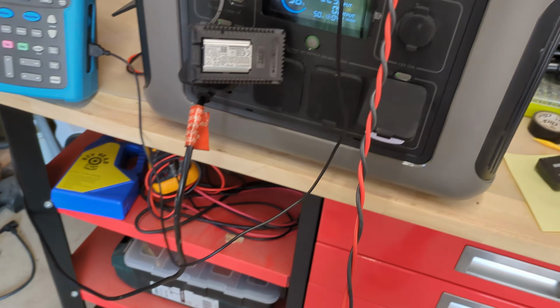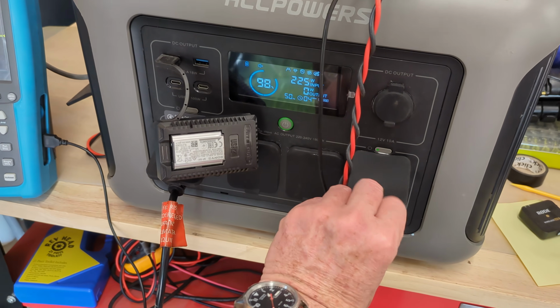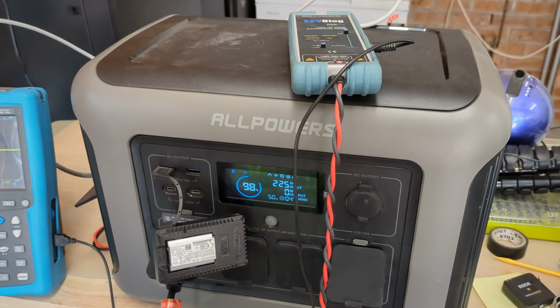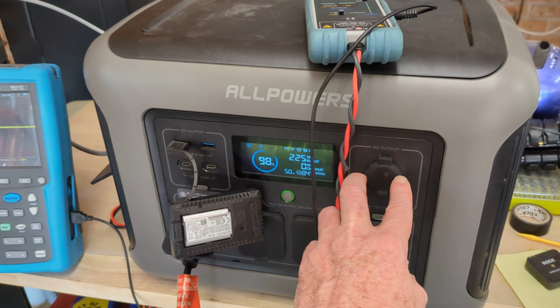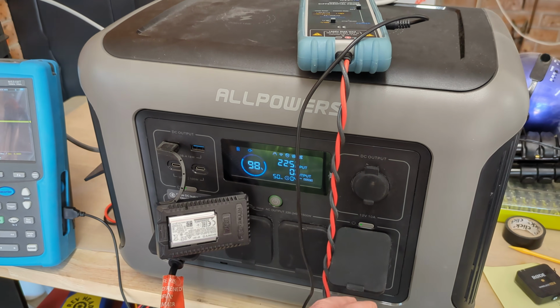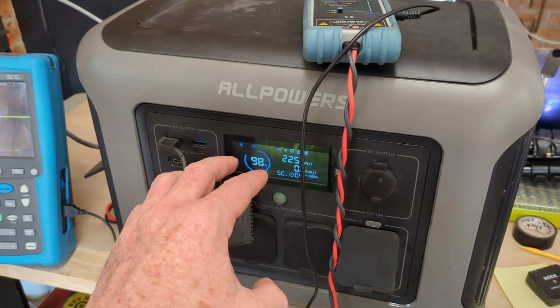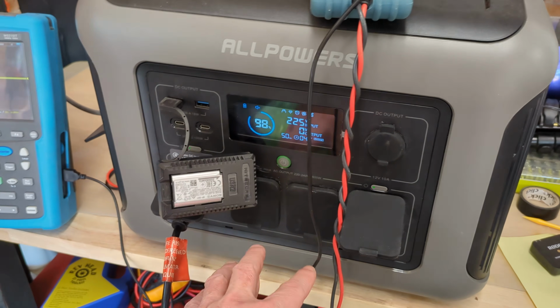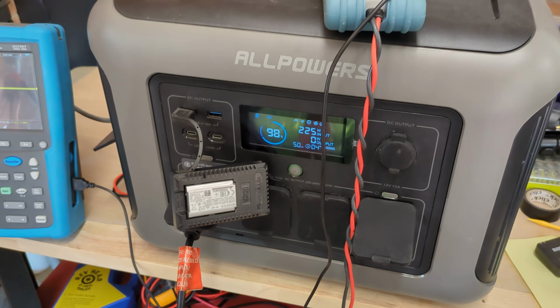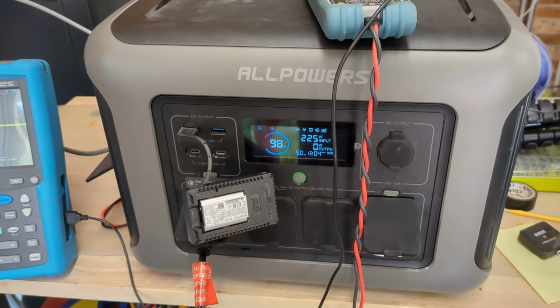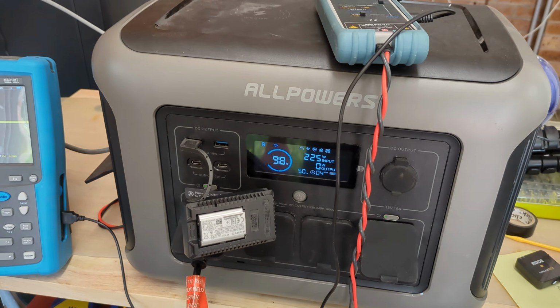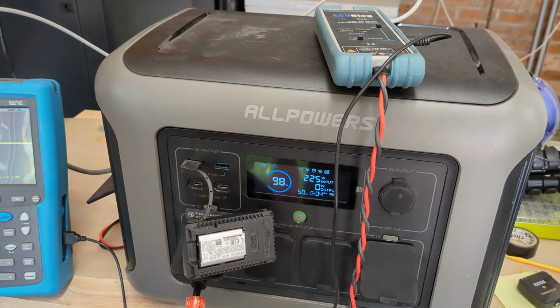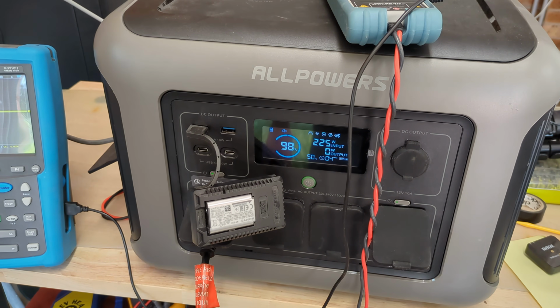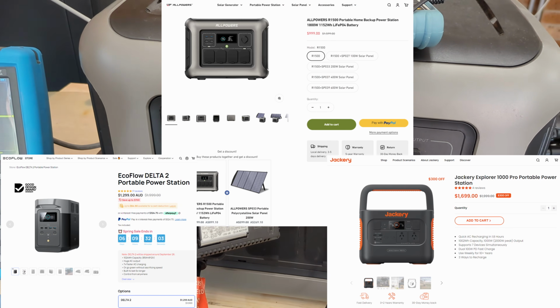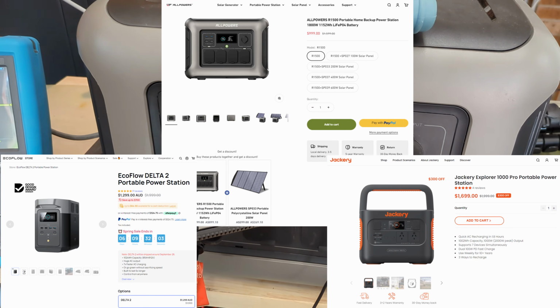I haven't actually tested based on the DC output, because you'll get higher efficiency with less internal losses in the inverters going from the DC battery to DC output rather than stepping up to 240 volt AC mains. There'll be less loss there, but on 240 volts I was not able to get the full rated capacity out of the thing. So you'll either find that acceptable or not - you'd have to do a complete shootout with other similarly priced models on the market.